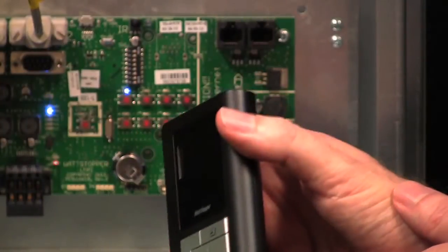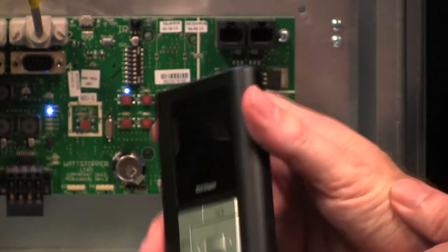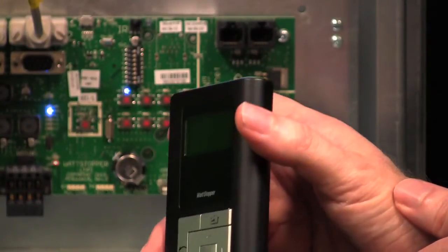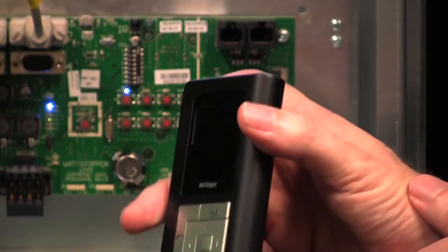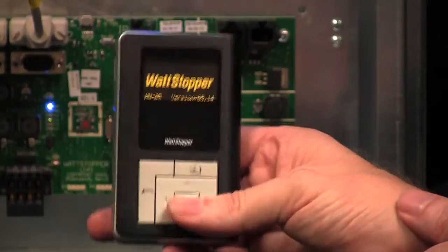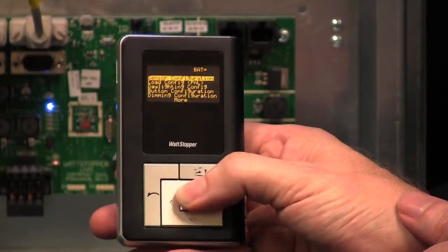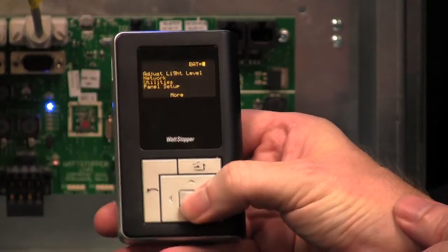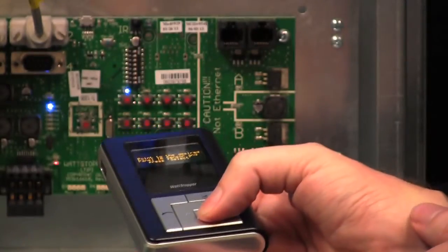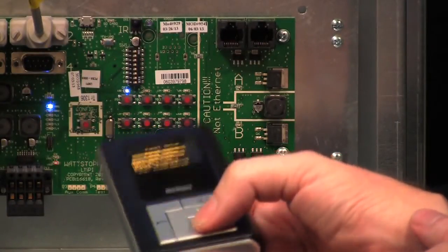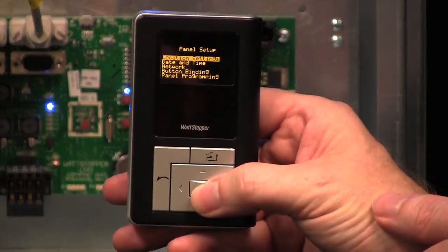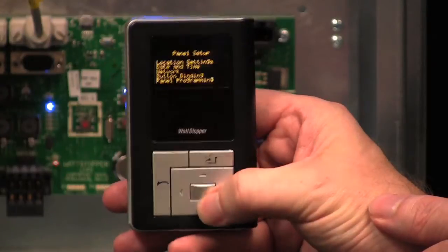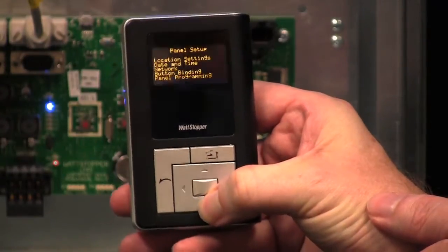So in order to set up the groups, we're going to do something a little different. We're actually going to use the LMCP to set up the group and then assign the parameters that we want for normal hours and after hours. We're going to turn on the LMCP, go down to the More option, choose Panel Setup, point it at the IR port in the panel, and then we see now we've got our panel setup menu. If you recall, in order to get to the schedules, we're going to go all the way down to the bottom and choose Panel Programming.